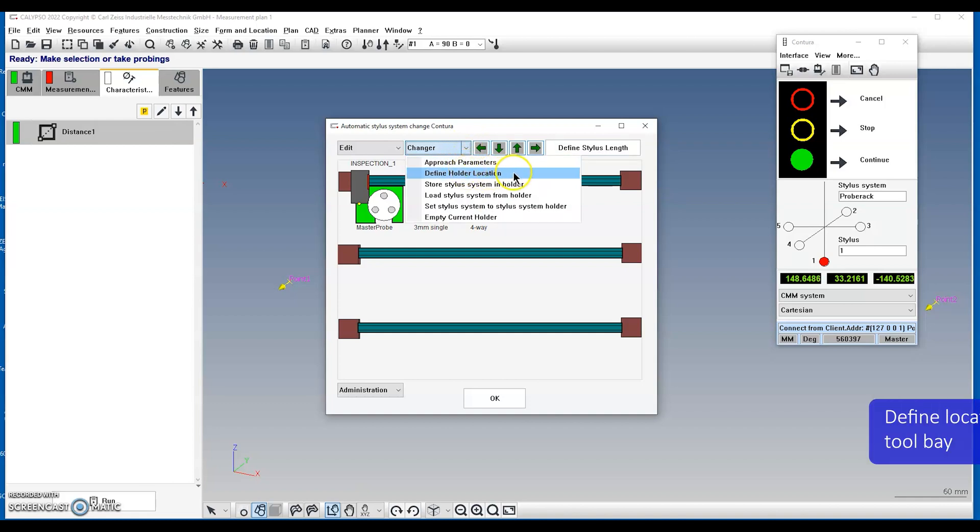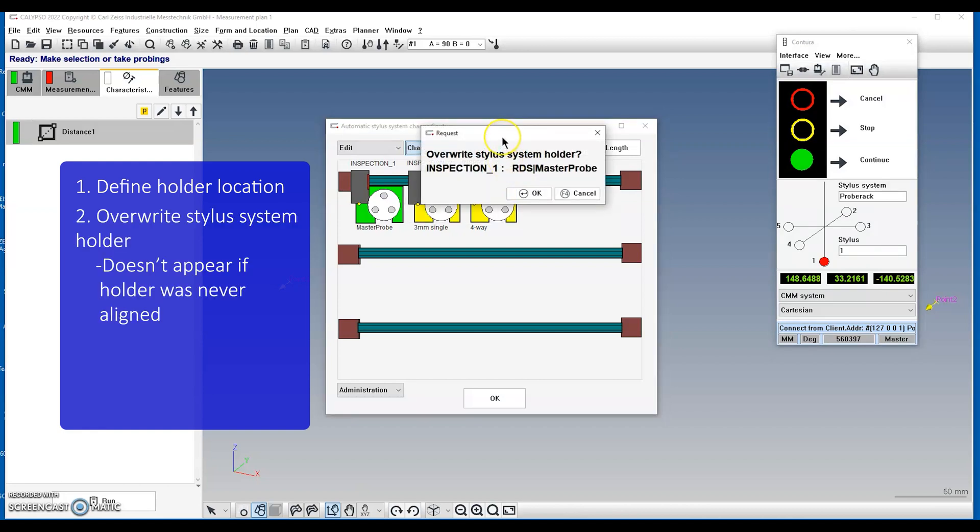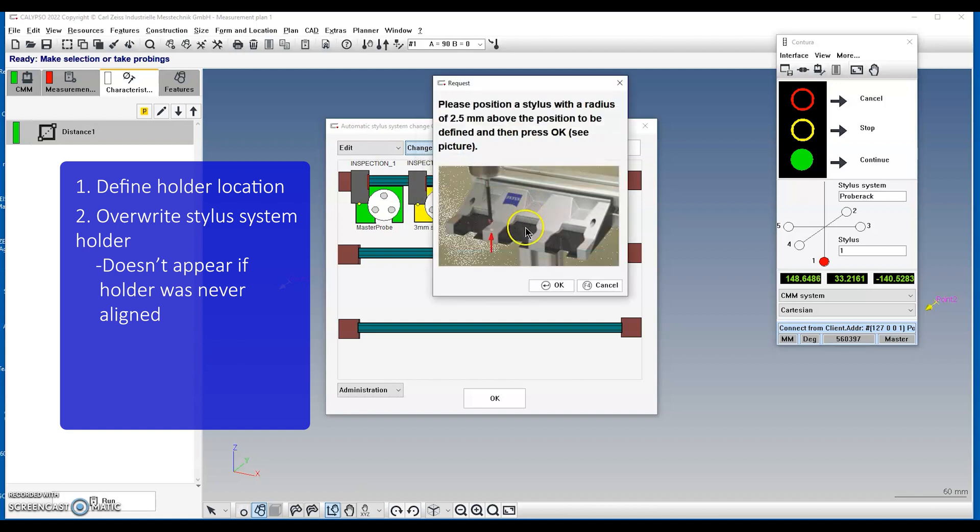Next, we're going to define the location of the tool bay or tool holder. To do this, click on define holder location. A window will appear to overwrite the stylus system holder. This window does not appear if the holder was never aligned. If you don't have a holder, it will add this to your screen. Click OK.